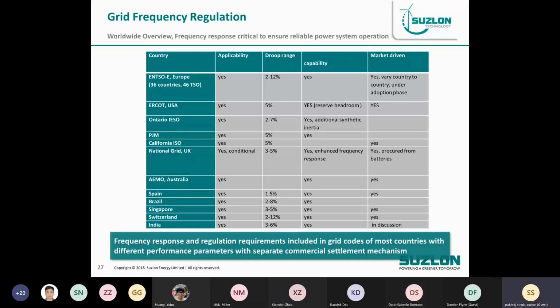But wind turbines can still provide this feature, the synthetic inertia, by slowing down the rotor, and the response time is not a problem. Looking at the frequency measurement that we do, it is possible to measure the change in frequency and the rate of change in 20 to 40 milliseconds. But the question is, how reliable is that? Because sometimes in small grid disturbances, the frequency cannot be read, calculated or measured very reliably.